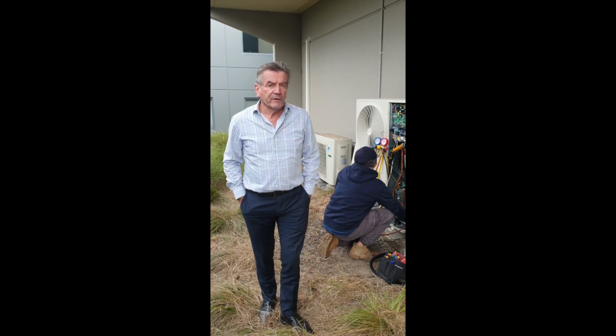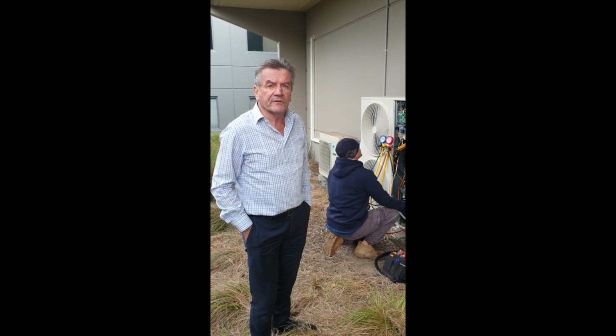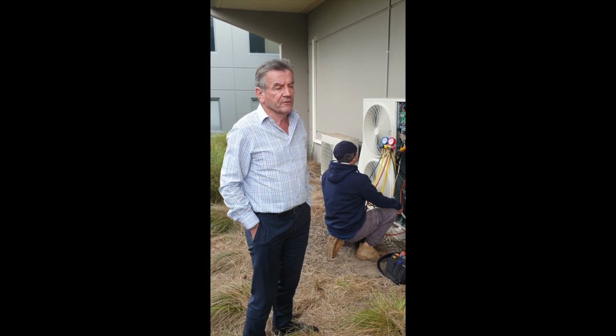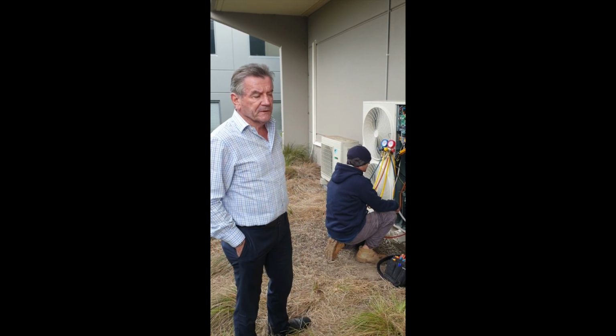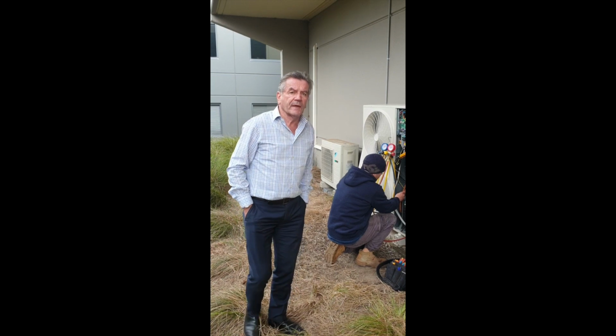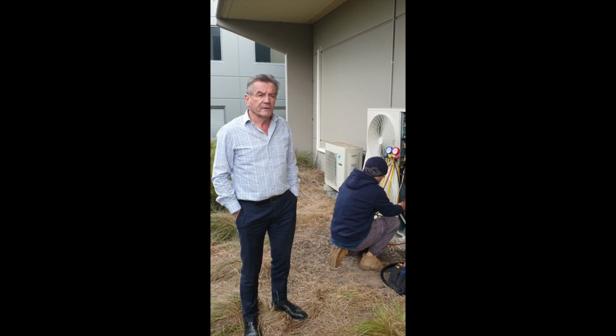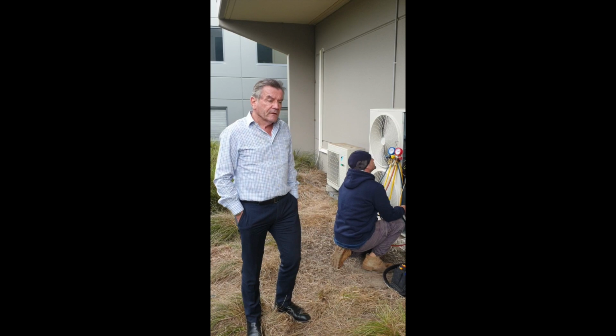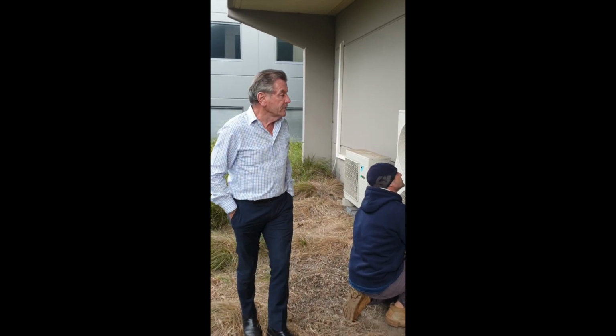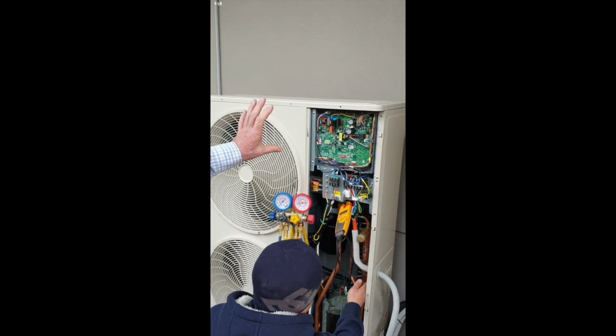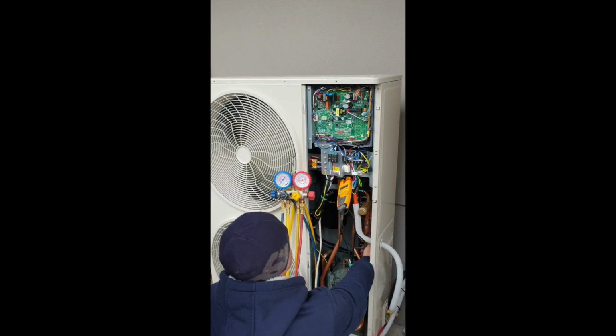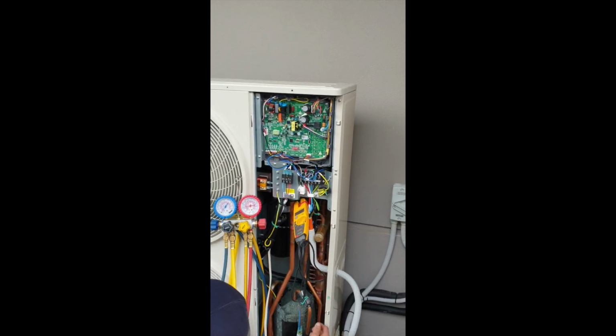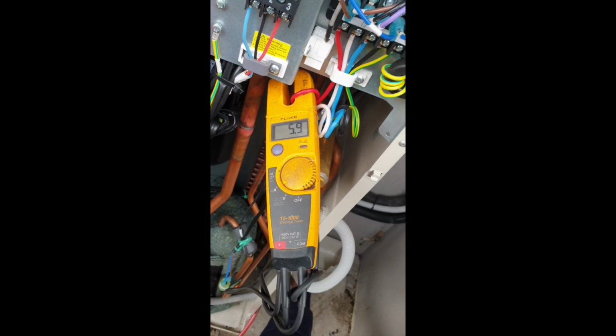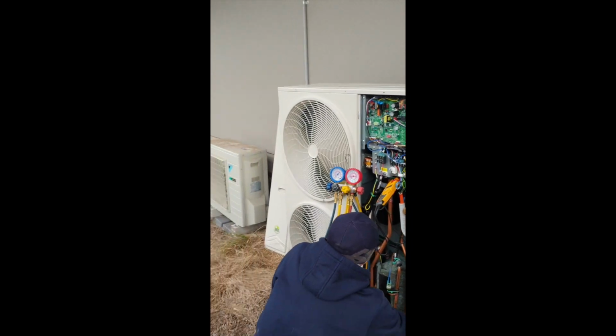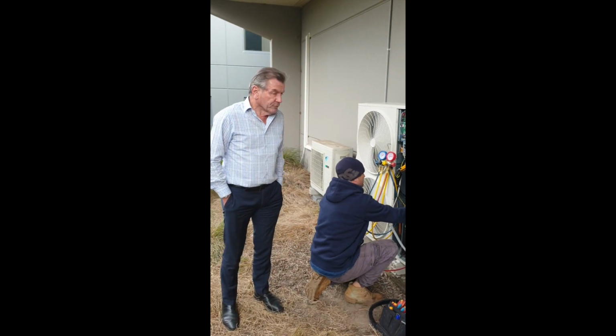Hi guys, we're back with the commissioning stage of the Polaris Intelligent Series machine. This is a 16 kilowatt 3-phase machine. It's currently drawing about 6 amps only, and it's on full speed, on the full capacity on heating now. If you just come forward, you'll see more closely the quality of the control. The build quality is very high. This machine is now drawing 5.8 amps, which is very low for this high capacity machine. This is the noise rating on very high speed. It'll wind back later. The machine will be here for an awfully long time.